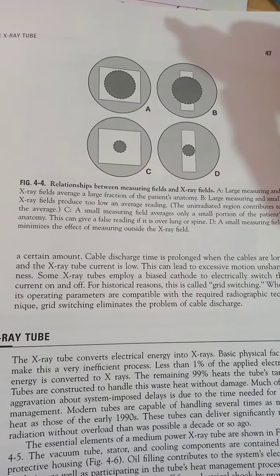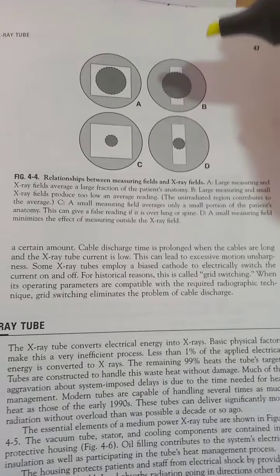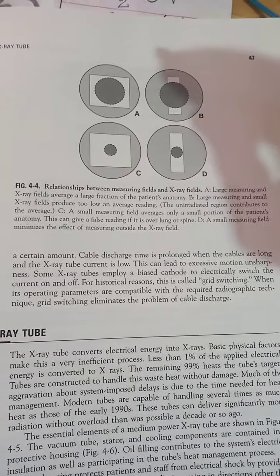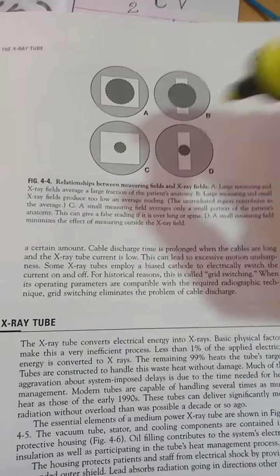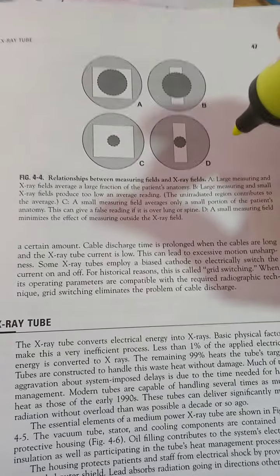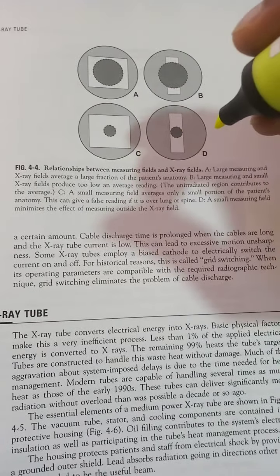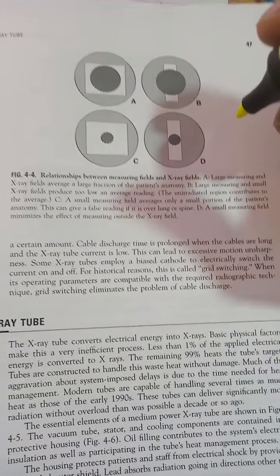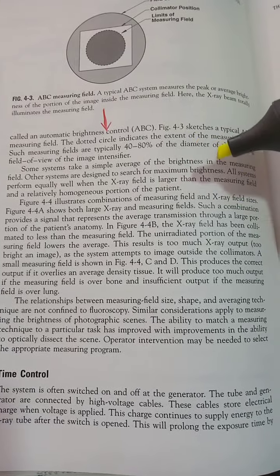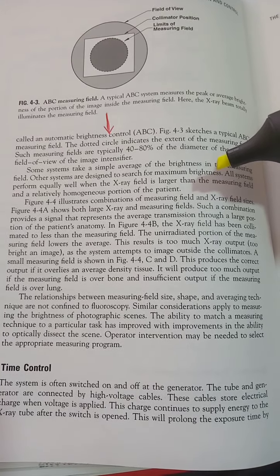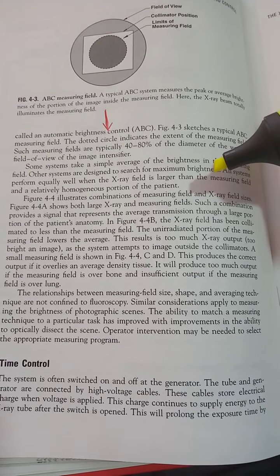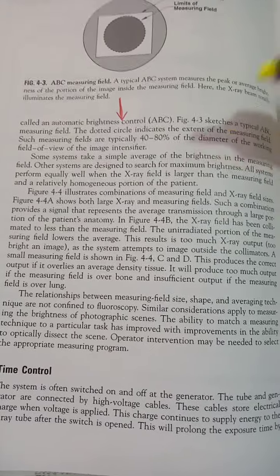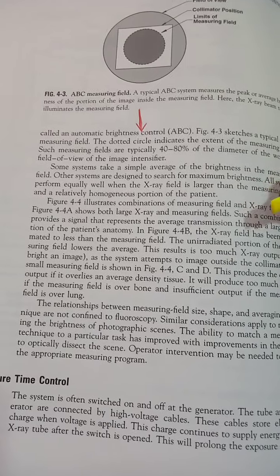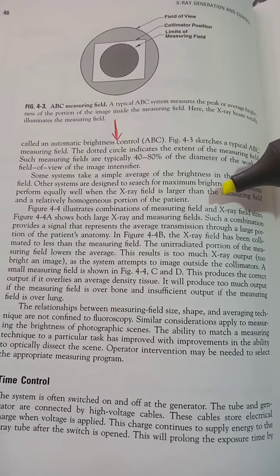So there are conditions where the X-ray field is bigger than the measuring field, or where the measuring field is bigger than the X-ray field, or where the X-ray field is equal to the measuring field. All of these three or four conditions need to be managed in an astute manner, so that the patient gets the best combination of dose and accuracy and the least amount of scatter, so that the image produced is extremely accurate and facilitates diagnostic precision. So this figure that I just showed you illustrates combinations of measuring field and X-ray field sizes. Such a combination provides a signal that represents the average transmission through a large portion of the patient's anatomy.